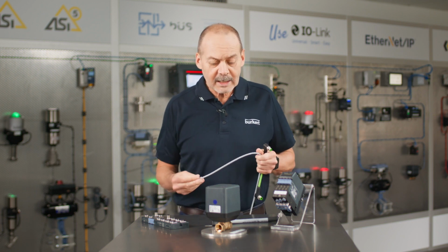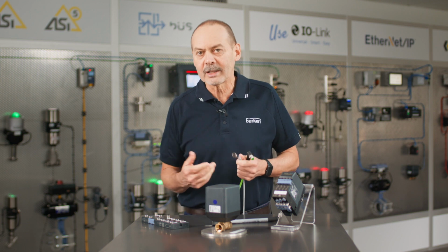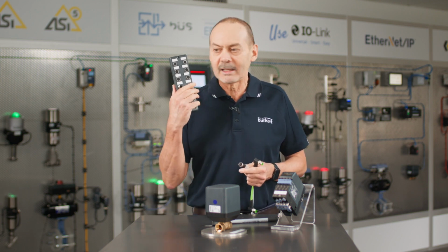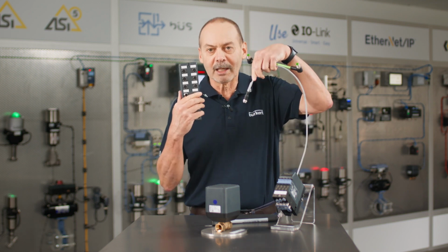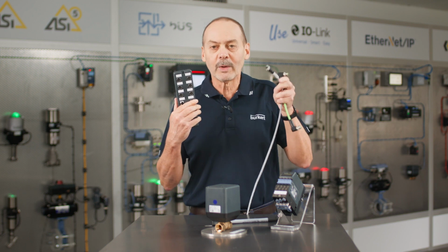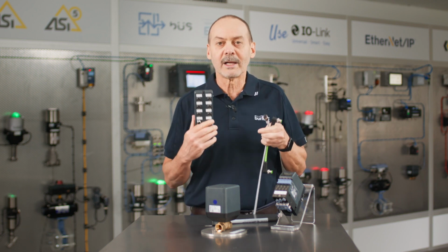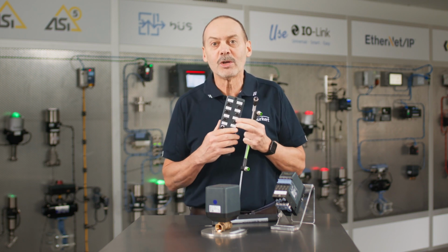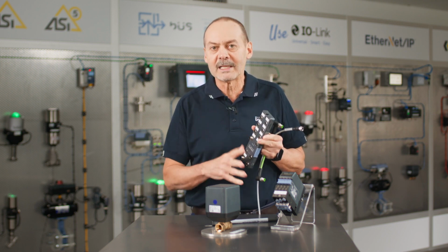Okay, for starters, when you're running cables in the field during installation, construction sites are messy, they're wet, they're dirty. Quite often we see blocks getting mounted in the field with open ports, as well as cables hanging beside them, not yet terminated or connected, also with open ports and terminations, and there's water and sprays and things like that. Anytime you put any of these devices in the field, make sure you cap them off, so that any of the environment, the dust and whatever, can't get in.